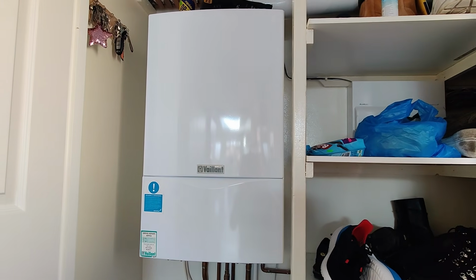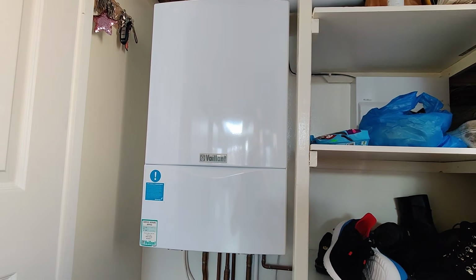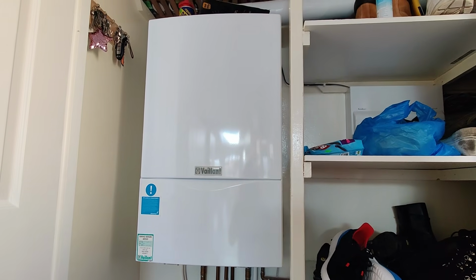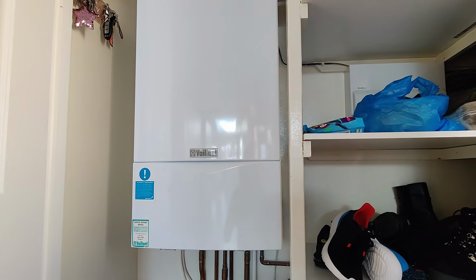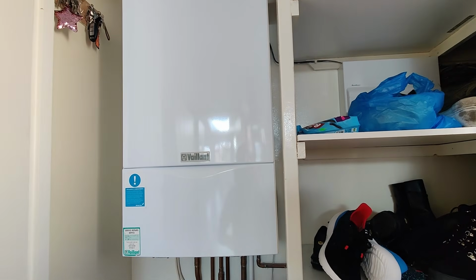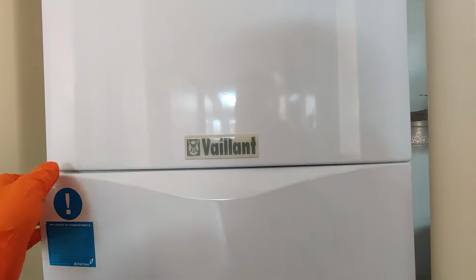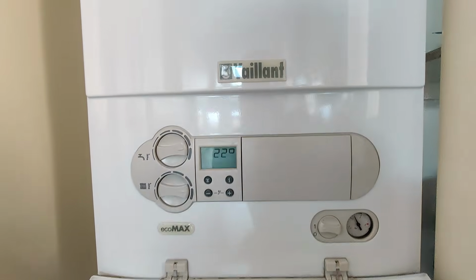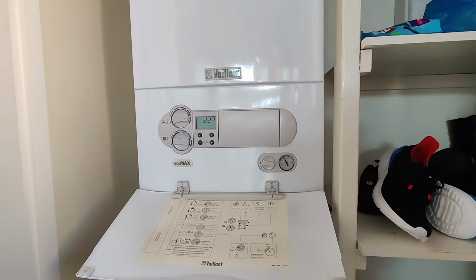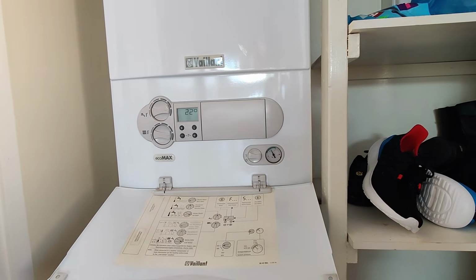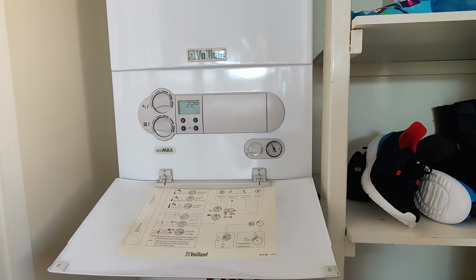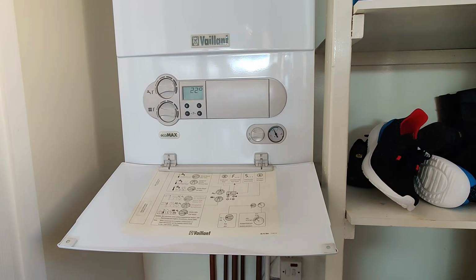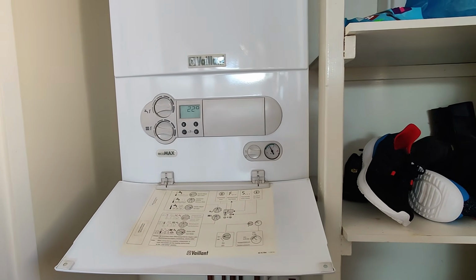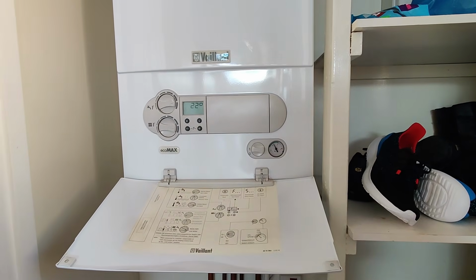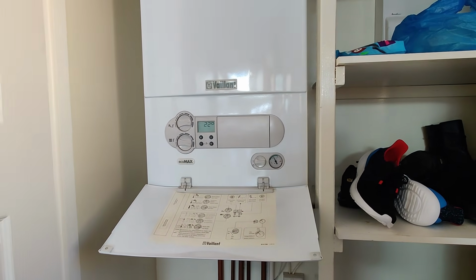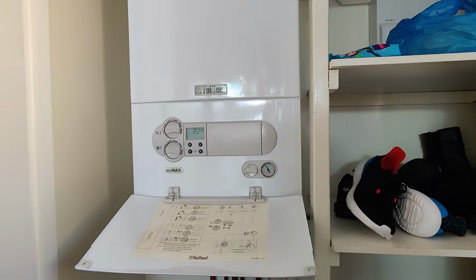Okay guys, so today I've been called out to a Vaillant Eco Max 35E. It's a very old boiler, about 25-26 years old, been working perfectly fine for this customer, and it's developed this fault where it's showing F28 fault code intermittently, which is flame loss basically. Could be contributed for many reasons really. It could be a PCB issue, it could be a gas valve issue, could be electrodes, could be the ignition lead. So we will do some testing today and find out what's causing this issue.